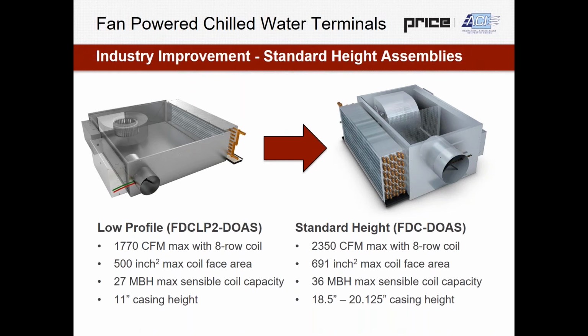It also means that zones with high loads can have, at many times, one piece of equipment, or a piece of equipment that can operate much more quietly, because as we reduce the footprint of the equipment and bring up the height, generally the sound power at matched CFMs tends to improve significantly.